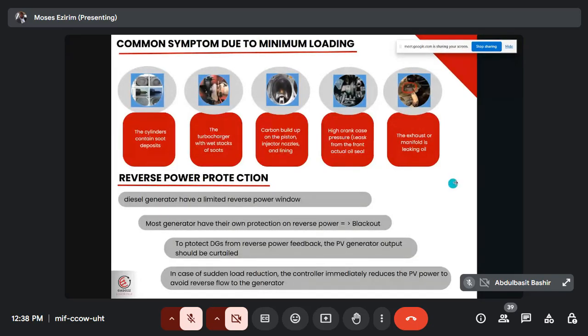All right. Now let's see reverse power protection. The diesel generator has a limited reverse power window. Now most generators have their own protection on reverse. So I think I've explained that to you. Some generators have a window. It can be that it can only withstand reverse power maybe 5 times before shutting down. Some have that protection. Once they see it, they shut down automatically.